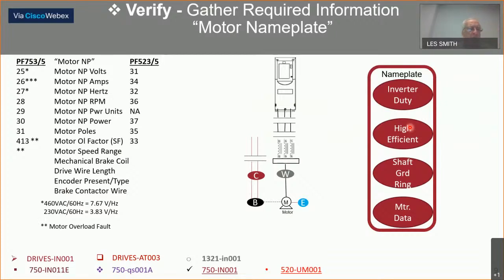Motor overload fault, we talked about that. This parameter is directly related to that fault. In other words, if you get a motor overload fault, it's relative to what you put in there. It could be a factory default at 1.0. It's not a service factor, but you may need to bump it up to keep it running. I had a fan in a hospital, in an x-ray room, where it pulled a tenth to an amp higher than what the motor nameplate was. But it didn't trip out until 12 to 20 hours later on the emergency room. So we bumped up the motor overload. That's what keeps it running, the motor overload setting.